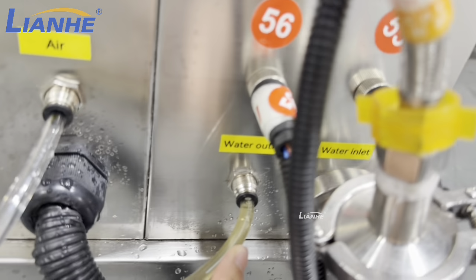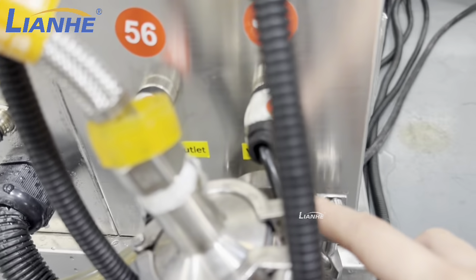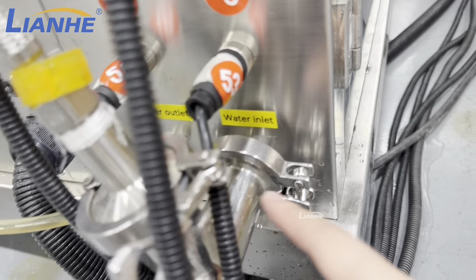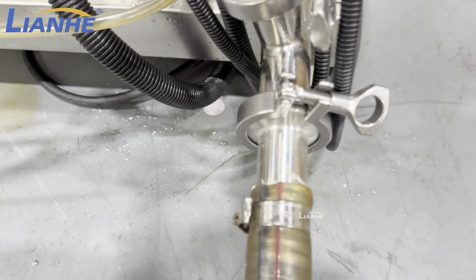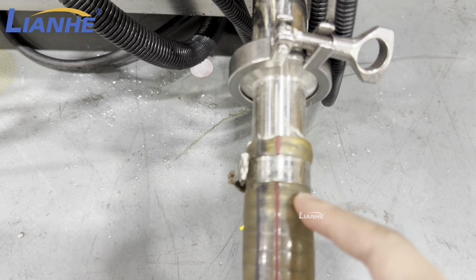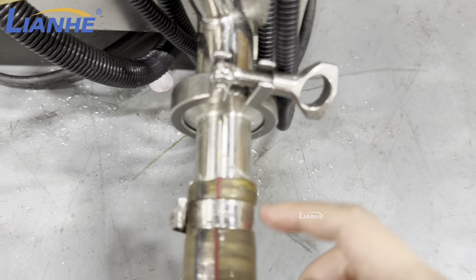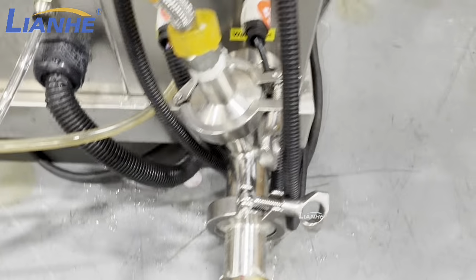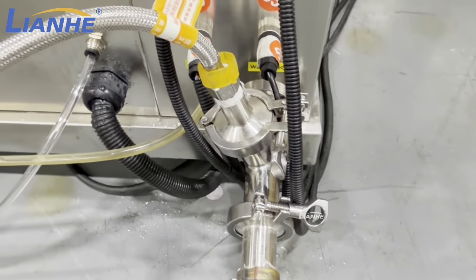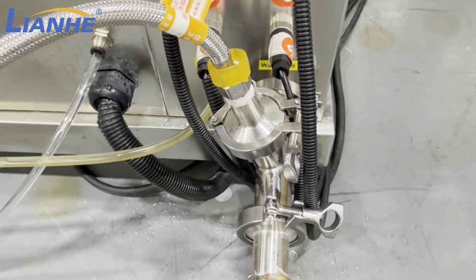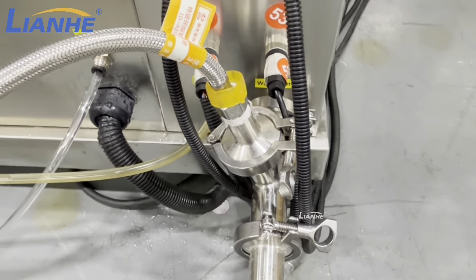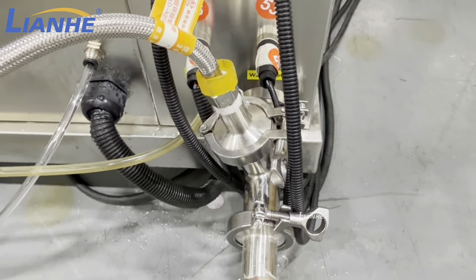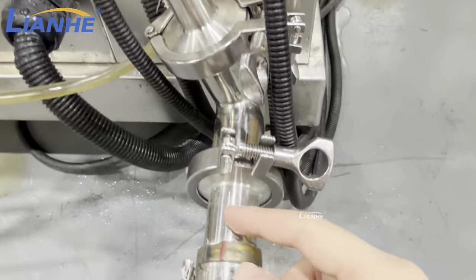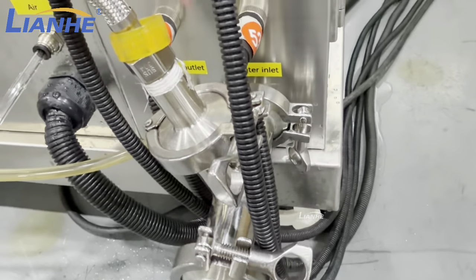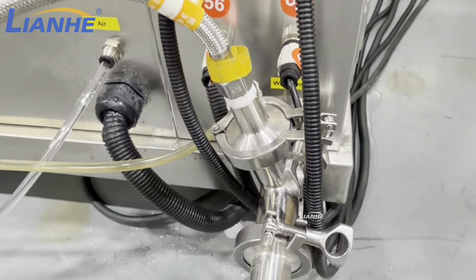And then for this one is the water outlet, and this one is the water inlet. You should connect the soft pipe here and make sure that this water inlet valve is open all the time, because you need to cool down the homogenizer when it's working, and also the vacuum pump, the homogenizer should use the water, so you should make sure that this water inlet valve is open all the time.